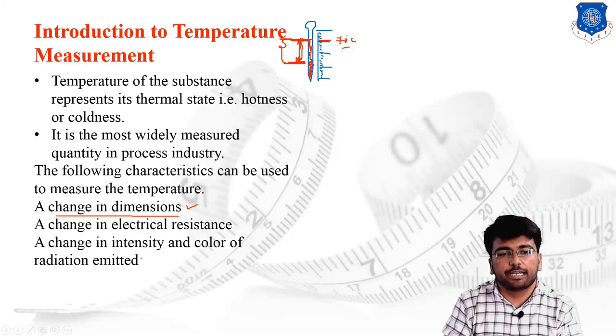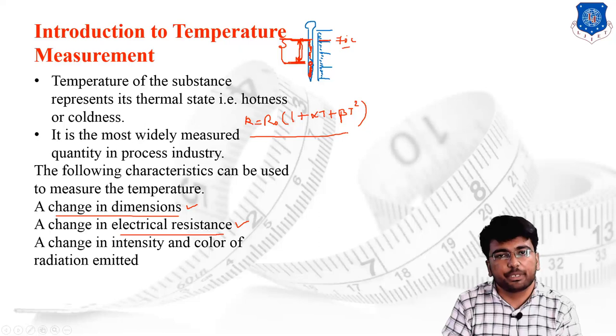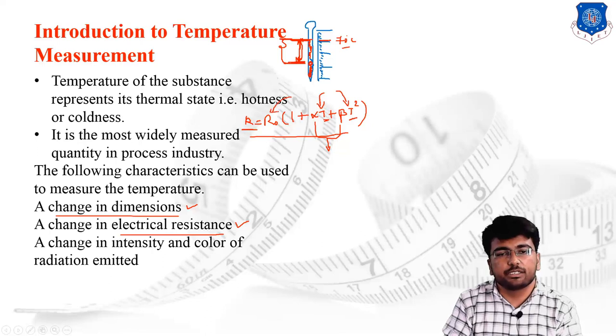The second characteristic is change in electrical resistance. By checking the change in electrical resistance, we can measure temperature. The equation is: R = R₀(1 + αT + βT²). This equation shows the positive change of resistance with temperature. Whatever resistance change occurs will directly reflect the temperature of the body. Here, alpha and beta are two different material constants, T is the temperature of the given body, and R₀ is the resistance at 0 degrees Celsius.